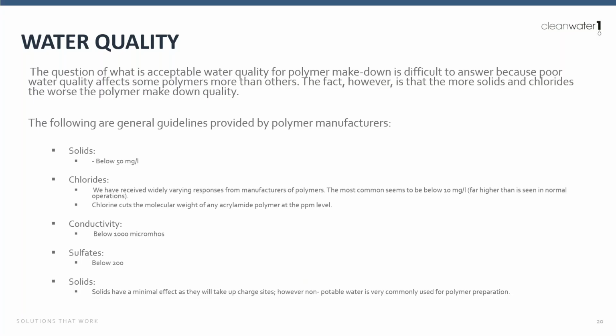But what happens is chlorine actually cuts the molecular weight of any polymer at the part per million level, so it actually degrades that polymer. Conductivity, we're looking at below 1,000 micromhos. Sulfates below 200. We already talked a little bit about the solids level, but this is important. It has a minimal effect on the overall polymer itself, but as soon as those solids come into contact with the polymer, the charge sites on that polymer molecule start to be taken up.